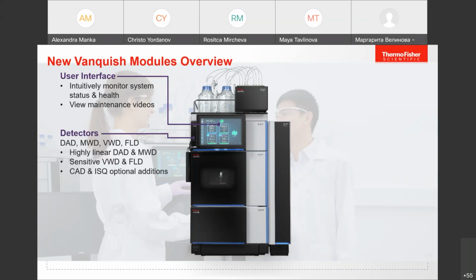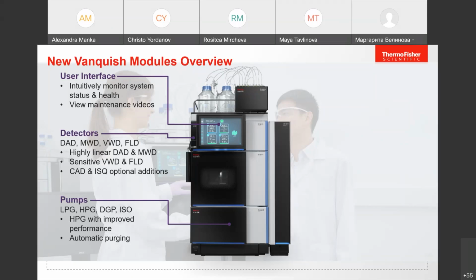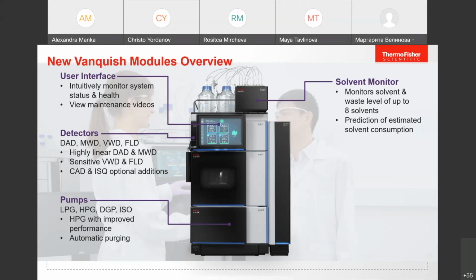Then for the detectors, we have here a wide range of detectors, like the diode array detector, the multiple wavelength detector, the variable wavelength detector, or the fluorescence detector. Of course, the charged aerosol detector and the ISQ EC or EM can be added as optional additions. For pumps, we offer different pump types, like the low pressure gradient pumps, the high pressure gradient pumps, a dual gradient pump, or isocratic pumps. Another new feature is that we do automatic purging of the pumps.